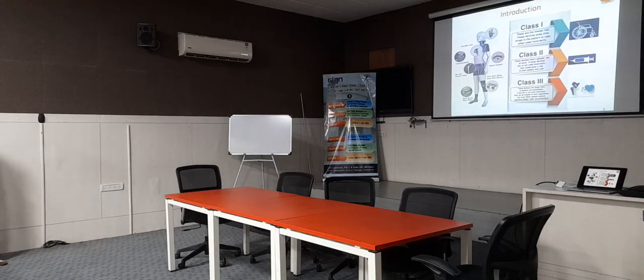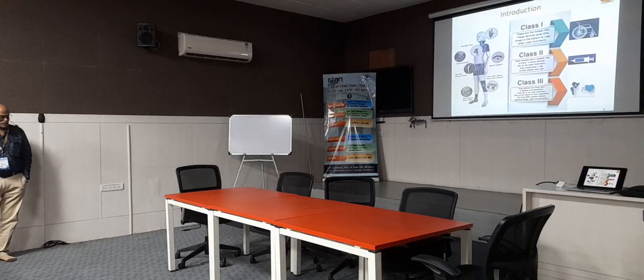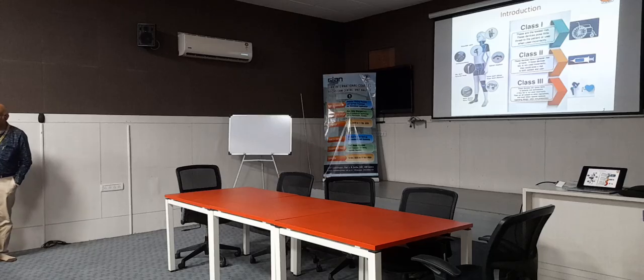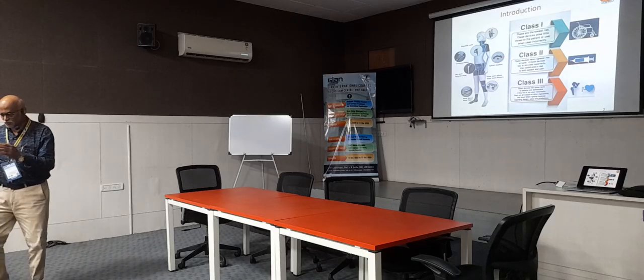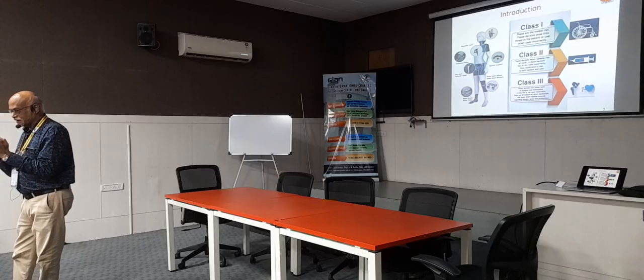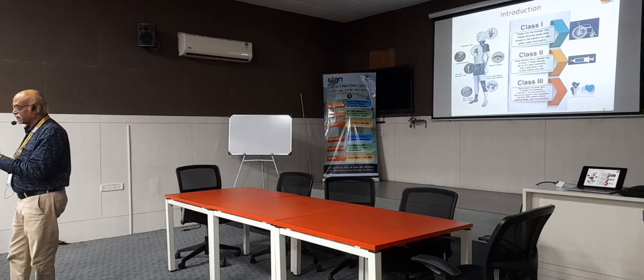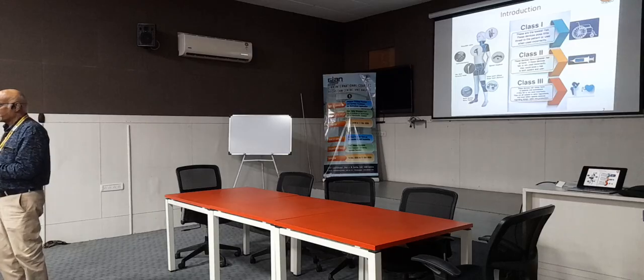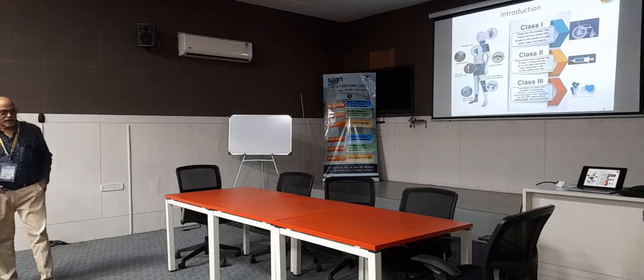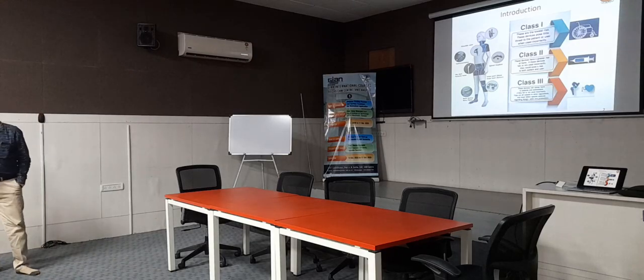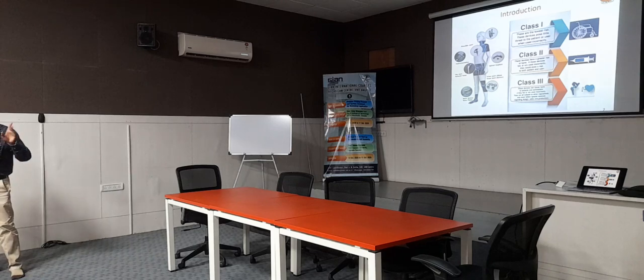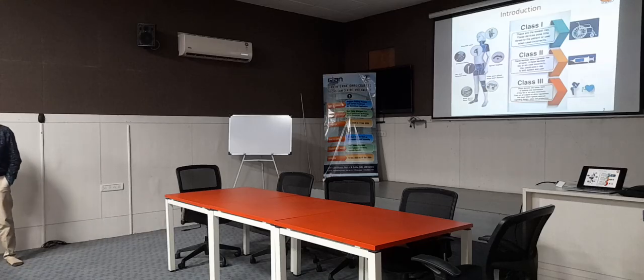Now let's look at the introduction. I told you in my last lecture also that medical devices are classified under class A, class B, class C and class D. At international level, they are classified as class 1, class 2 and class 3. It is rather simpler than our ABCD. But in the Indian scenario, they talk about ABCD, and that C and D are actually involved in class 3. So it is A, B and CD. That's what you can see.